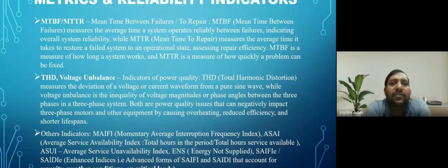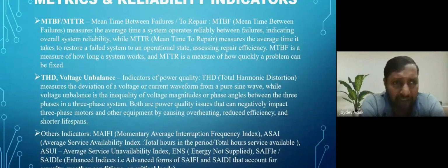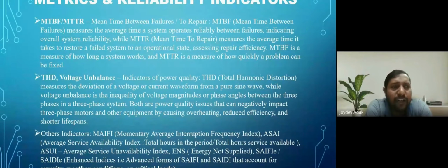That means if MTTR is less, it will be considered a faster recovery system, as it can recover the system from faulty to normal condition. MTBF should be greater for a reliable system, and MTTR should be very less. And next is THD and voltage unbalance. THD, total harmonic distortion, and voltage unbalance are also reliability factors based on which we can decide whether the power quality from that DISCOM is acceptable or not.